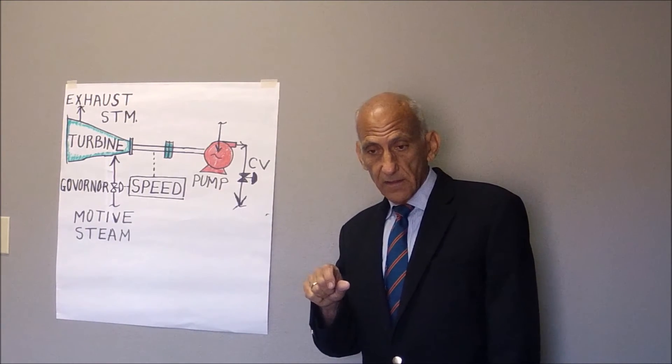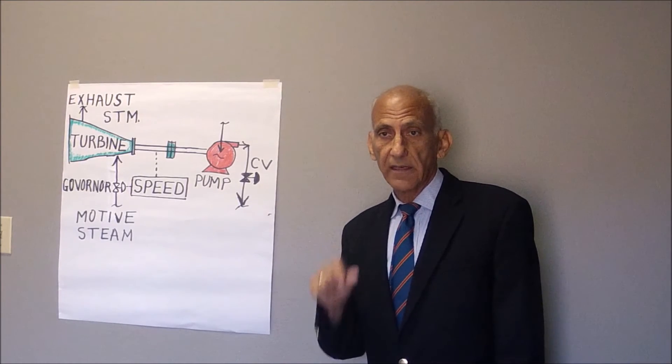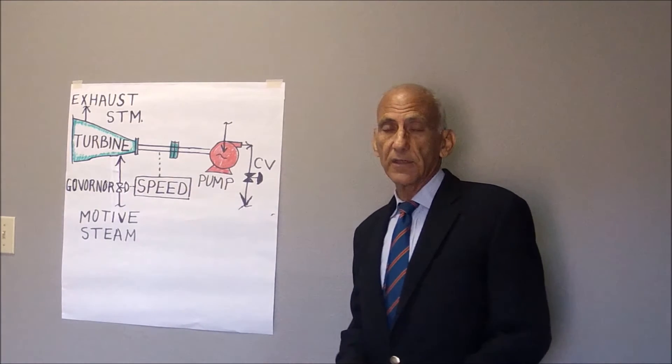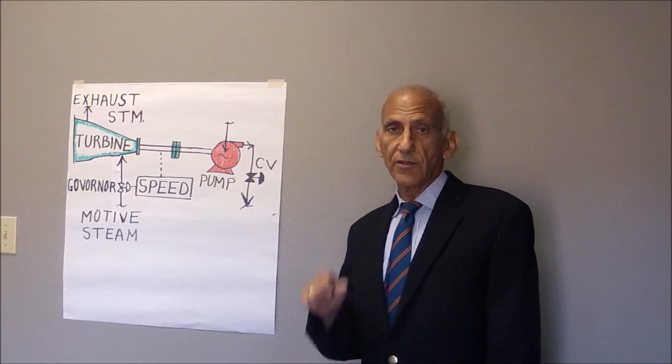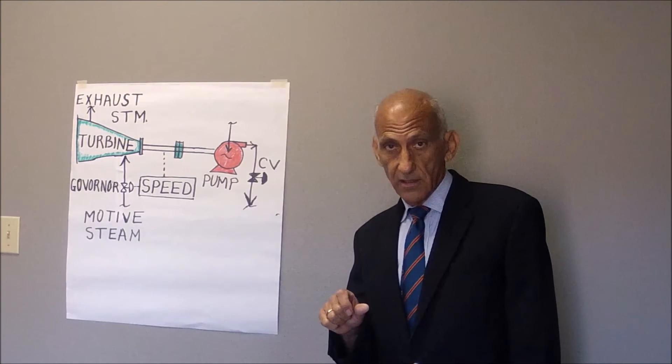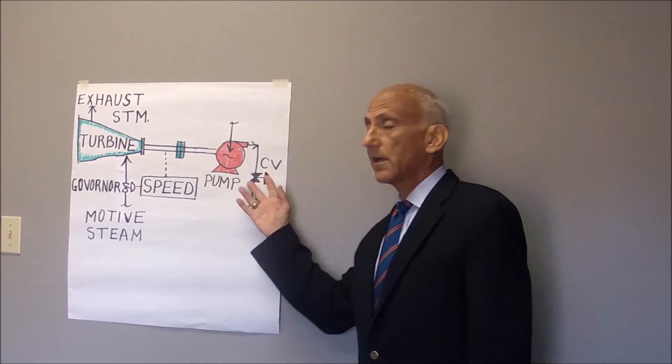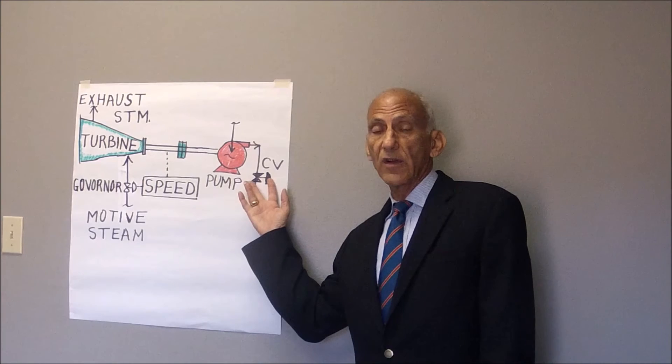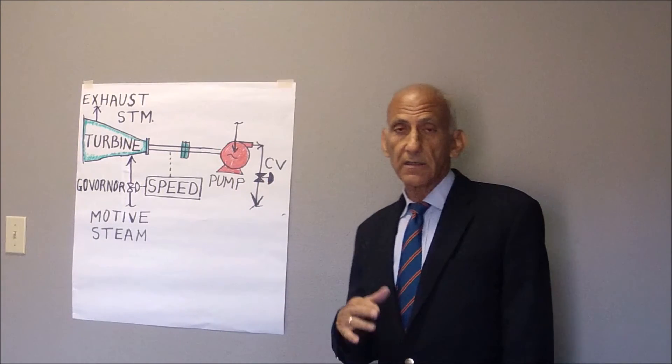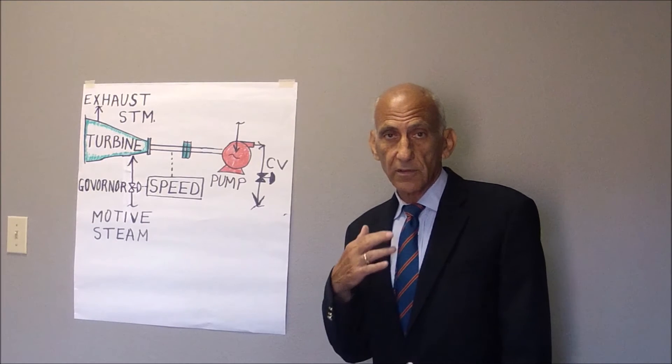You slow the turbine down, the governor's speed control valve will now start to close, and the control valve on the discharge of the pump will start to open.